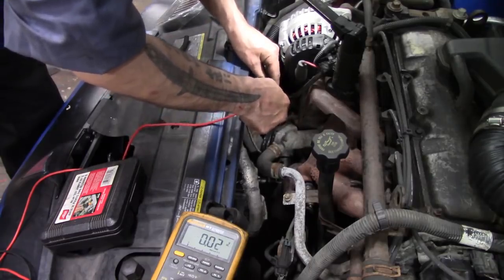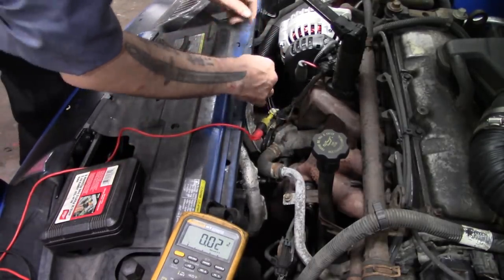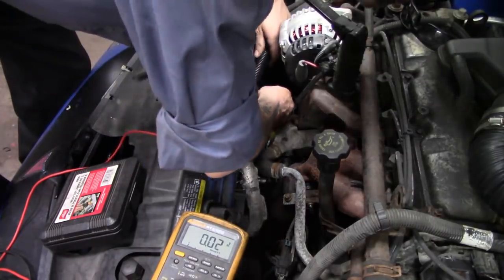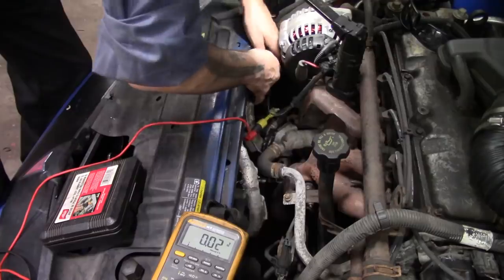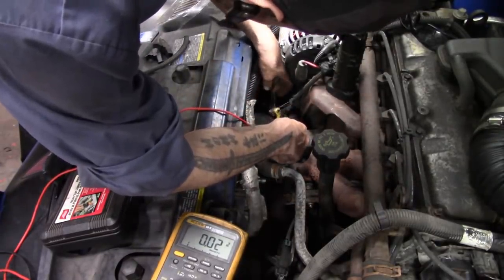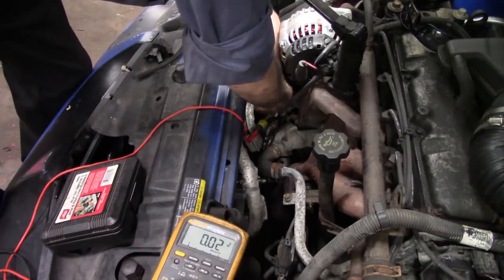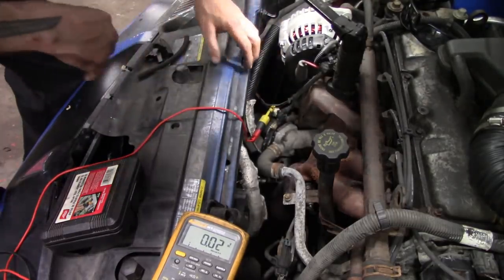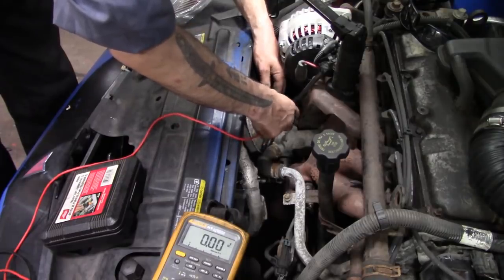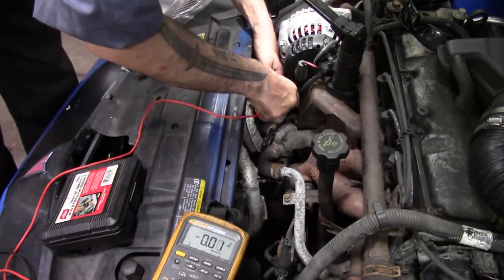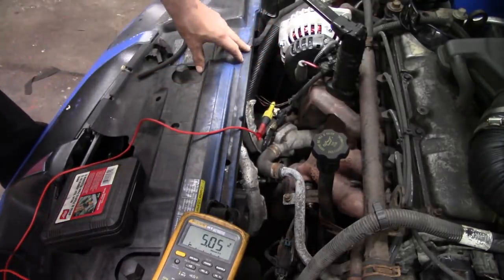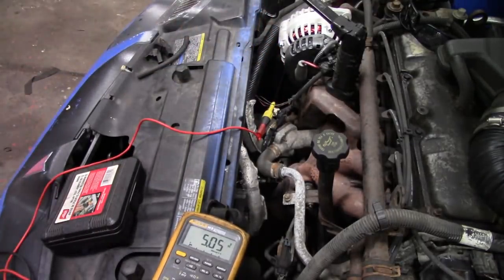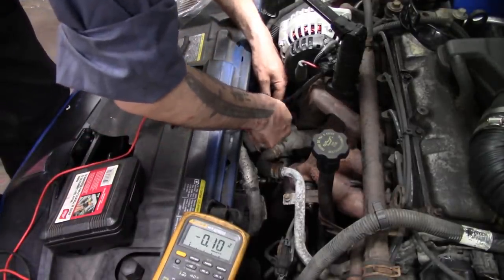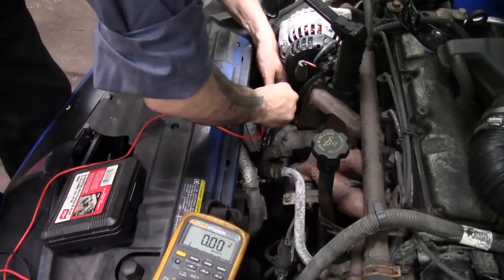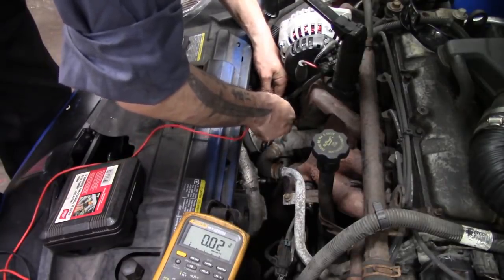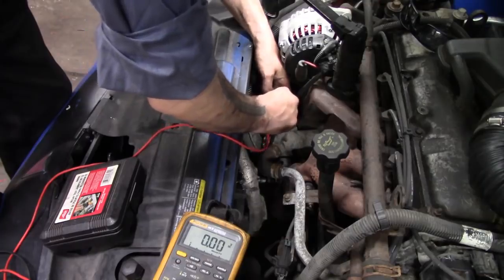Okay, now I'm going to leave this on the signal and plug it in. And I'm still at 0. I'm going to go back to my 5-volt reference — my 5-volt reference is still there. So what is that telling me? Well, that is telling me either 1, I have no refrigerant in this system, or 2, I have a broken sensor.